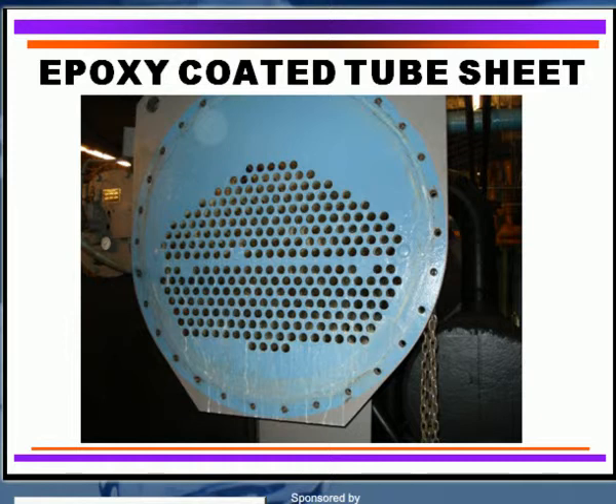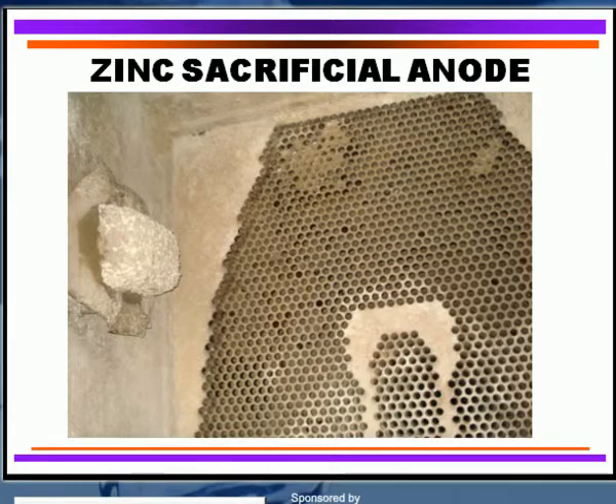Some people have actually used other techniques too, which are still worthwhile, and that's the use of the zinc sacrificial anode. That's an example of it, the block on the left-hand side. This happens to be in a utility power plant condenser. The zinc sacrificial anode corrodes in preference, protecting the metal surface around it, so it has to be in direct contact with the metal surfaces you want protected. It'll corrode, and of course the zinc will go back into solution and be carried around with the circulating water. Soluble zinc salts are a corrosion inhibitor for carbon steel, so you get some benefit from that.